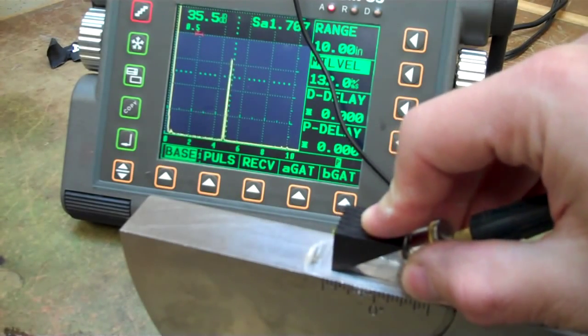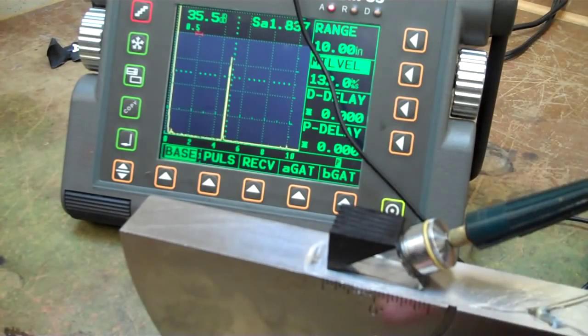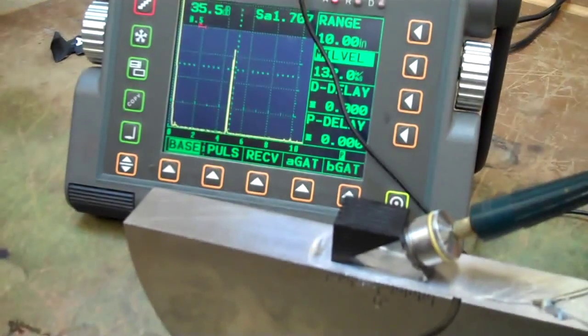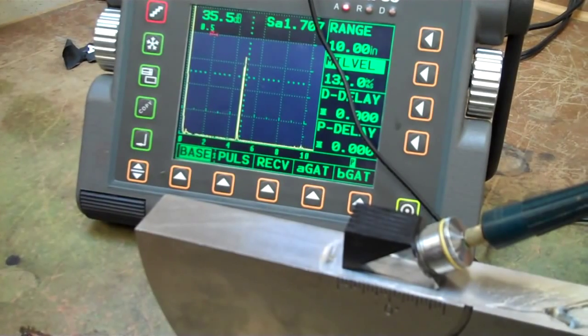So we peak that signal up. Look right over the side of the block here, which I'm going to take loose for a second. So we look right over the side of the block to see if that beam exit point is right over that 0, which it's a little past, but not too horrible. Okay? Wipe the couplant off, make it a little easier to see. Alright, so we're pretty close there. That's part A. Okay? Sorry for all the rattling around here. Just need you to be right in the middle of the action.